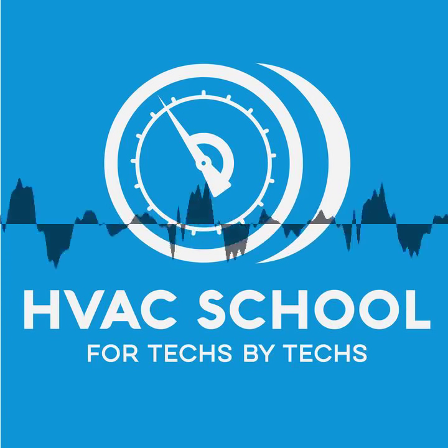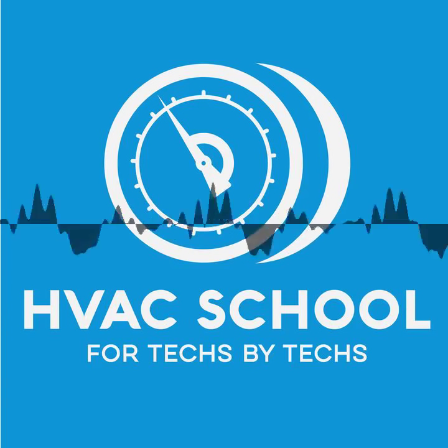And the ten-wrap amplifies your current reading by 10 times. So little bitty current readings, small current readings, are amplified by 10 times. So for example, if it reads 12, you get a 12 amp reading, you divide it by 10, and you've got a 1.2 amp reading, which is very hard to resolve on some amp meters. Exactly.